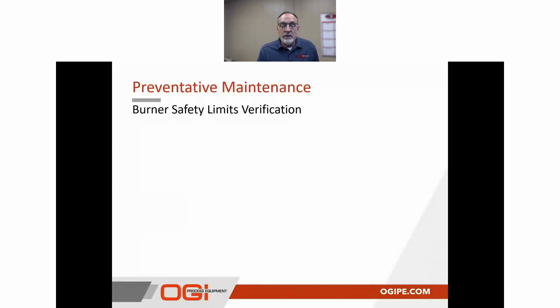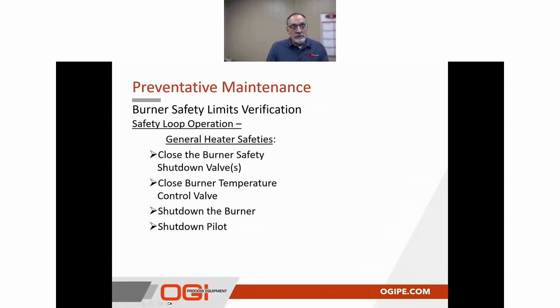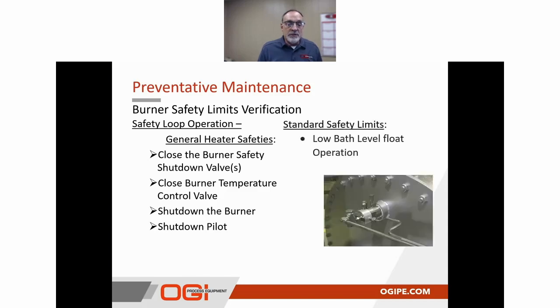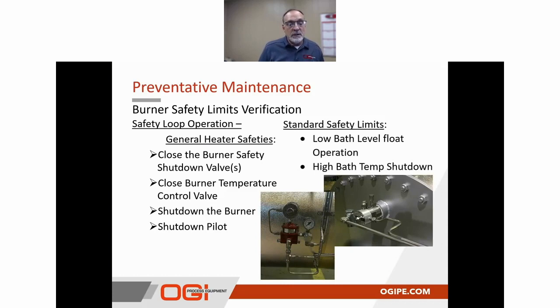For each type of control, the shutdown of the main burner and the pilot, when applicable, will be verified for each of the instruments. In this case, the general safety limits that we'll be reviewing will shut down the main burner shutdown valves. We'll close the burner temperature control valves, shutting down the burner, obviously, because there's no gas flow to it. And then we'll shut down the pilot assembly and the pilot with those general shutdowns. Those general safeties include both the low water level switch and the high temperature switches. Now, this is the minimum. Obviously, there could be other general heater safeties, not burner specific, that could also include a high process temperature alarm, either at the outlet of the heater or at the outlet of the regulating system.